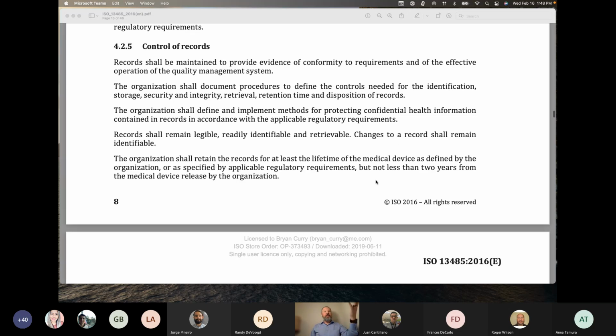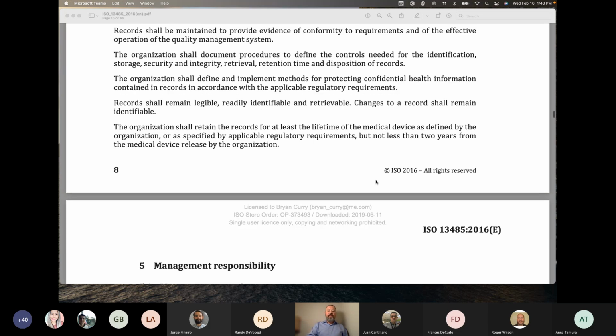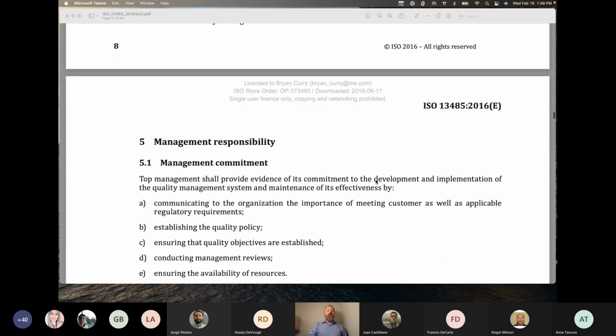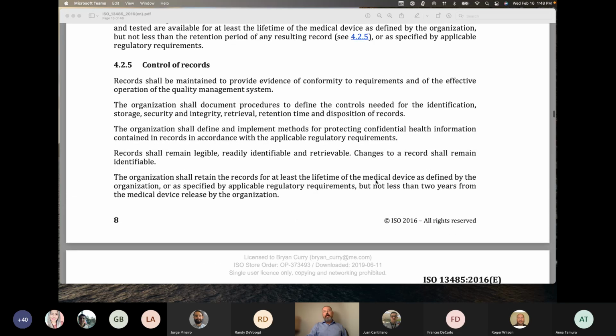And then again, in the same way that we retain procedures or documents, we are going to retain these records at least for the lifetime of the medical device, but for not less than 2 years, with the intent, again, that we could recreate our quality system at some date in the past in order to demonstrate conformity of a specific medical device that was manufactured on a specific date. And with that, we complete section 4 of the ISO regulation.